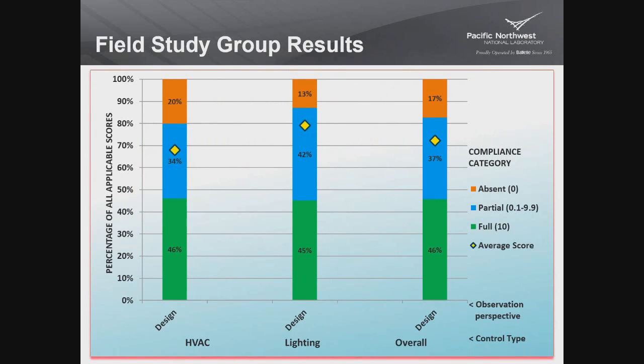This next chart, these bar charts, we split up the 14 requirements into HVAC, lighting, and then the sum of all the requirements. And this green portion shows us, if we look at the design of the HVAC systems, we see that 46% of our observations got a perfect score of 10 for the design. Looking at the orange, 20% had a score of 0, was not included at all.